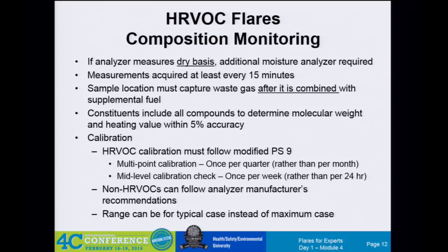But through doing all these different control projects on flares, and people are adding it in, the math gets a little more complicated when you're trying to control your system, because now you can say, okay, I'm over 300. Well, how much of that is supplemental fuel versus what was in my vent gas? The big driver is, I want to always be minimizing the amount of supplemental fuel I'm adding. So you always want to be able to back that amount of gas out to say, wait, I only need 100 SCF per minute of natural gas right now, not 50.